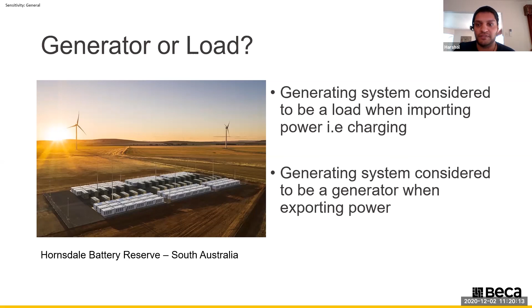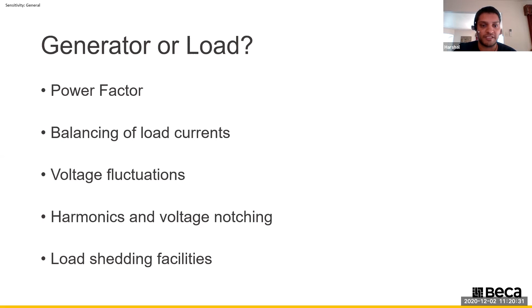So when acting as a load, some of the performance standards that need to be considered are power factor, balancing of load currents, voltage fluctuations, harmonics, and load shedding facilities, typical for a large HV connected customer. So nothing unusual there. But from recent experience, it has been quite interesting to negotiate performance standards for power factor and load shedding, given the battery is operating both as a generator and as a load. As a load, the battery system at its nominal voltage is typically required to operate within a power factor range of 0.95 lagging to unity. However, for a specific operating scenario when the battery is charging whilst also providing voltage control capability, the power factor may very well operate outside of the permissible range when it's attempting to control voltage, which is contradictory in terms of the prescribed performance standards at this time.